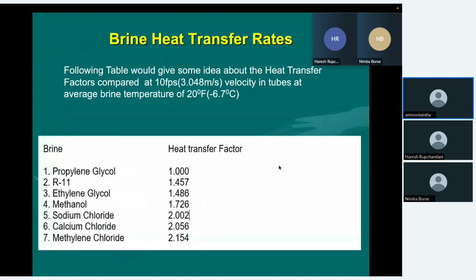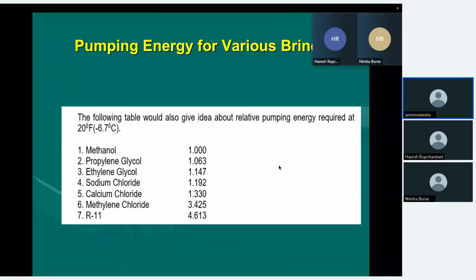Now, as you can see from the earlier slide, the heat transfer coefficient is very low. No heat transfer was taking place, no evaporation was taking place, and the entire liquid filled into the chiller was coming to the compressor. Finally, I had to drain the entire propylene glycol and replace it with water. Continuously, I was pouring water into the chiller and draining out the concentrated propylene glycol. When the concentration came near 40%, 30%, the liquid coming to the compressor stopped and the plant started working.